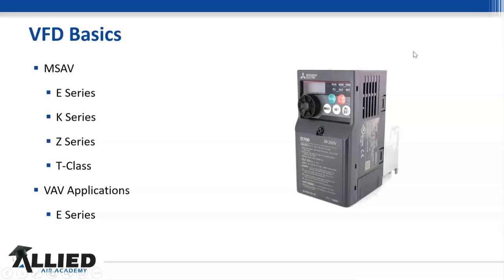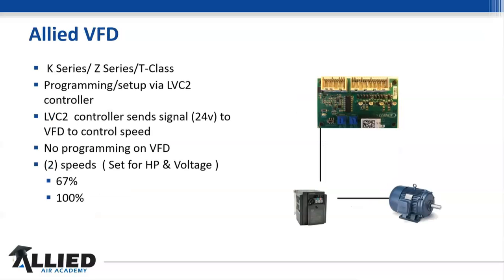So this is kind of what units we actually use VFDs on. E-Series, K-Series, Z-Series, we use them on a lot, okay? And it's just becoming more of the norm now to see these on units. But you also have a board that helps control this. Now, if we look at the K and the Z series, even the split series, you're going to see this board on there. And all the drives are programmed either from the factory or from Mitsubishi, one of the two, okay? So really and truly, you should not have to go into this Mitsubishi drive and do any kind of changing of the program, which makes it nice so you don't have to sit there and guess.